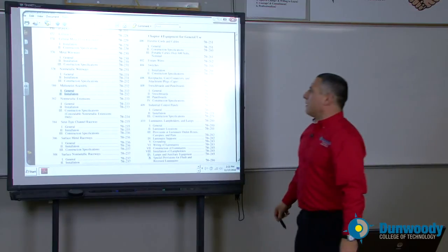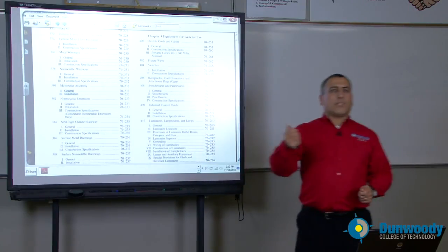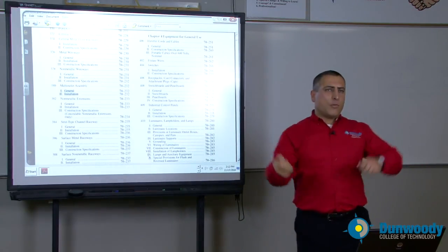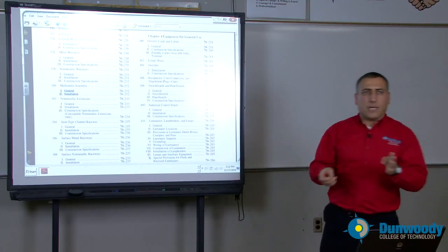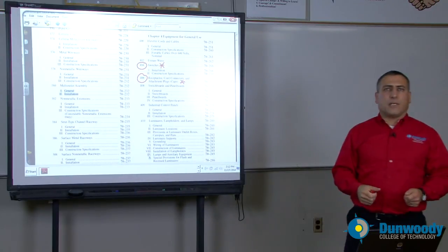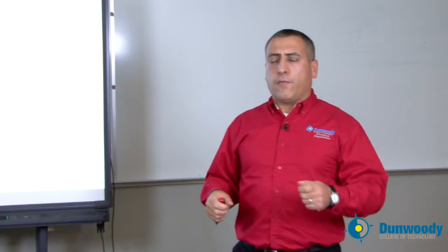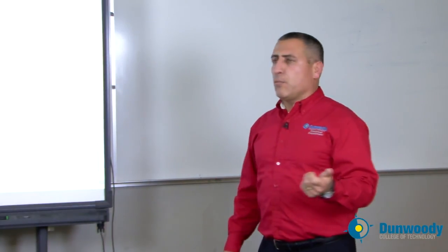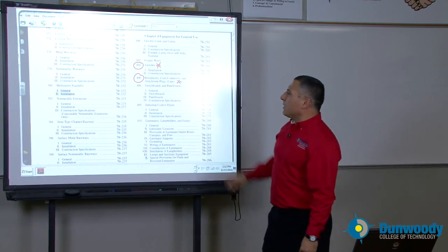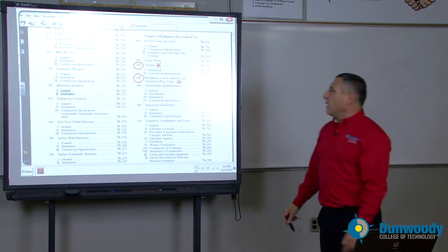If you need to understand the system well: how high can I put a switch off the ground? Can I mix a 120-volt switch with a 277-volt switch in the same box? No, you can't. You're going to find that in article 404, which talks about switches — must know. For receptacles: what size, where does code require a tamper-resistant receptacle, where does it require an arc fault circuit interrupter, where does it require a GFCI? All this information is in article 406.